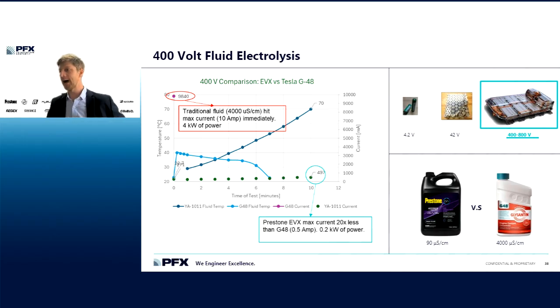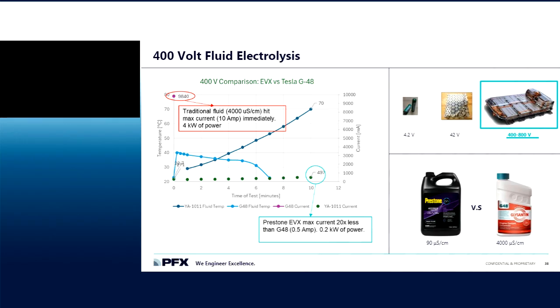Now, let's look at the high conductivity G48 type fluid. So this is a 4,000 microsiemens fluid, and this will be the next video that we're going to watch at 400 volts. And you'll see immediately we see a much more violent reaction. And if we keep an eye on this, about 8 seconds in, the hydrogen alarms go off because they've tripped for detecting their lower explosion limit within that laboratory.